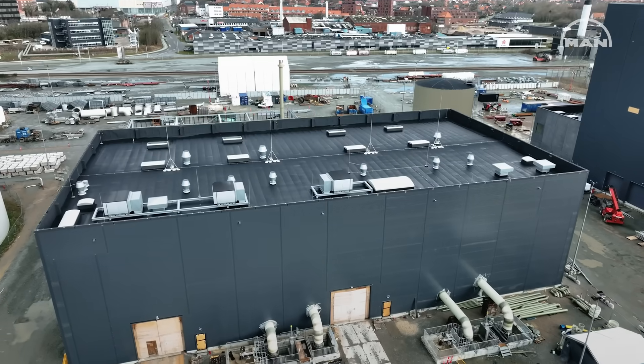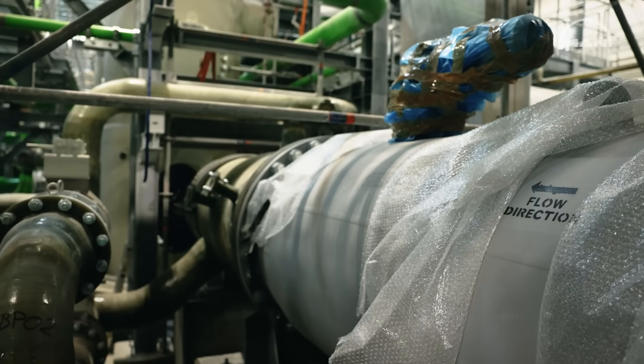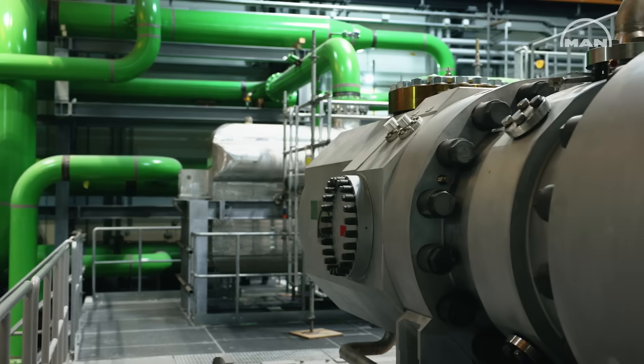From the inner harbour here we pump water up to the heat pump. It goes to the evaporator — which you can actually see here — where it evaporates CO2, then goes into a compressor that compresses it up to a critical pressure, and then it goes to a heat exchanger.